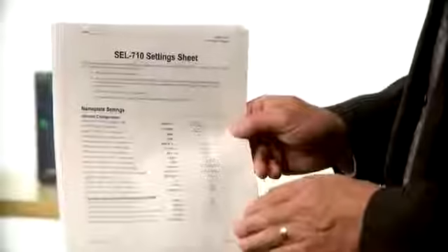So after pulling that information off of the one-line diagrams, I went through and just pulled out the motor data sheet. Basically, all the information we need to set the motor nameplate application in the relay is provided on this nameplate application data sheet right from the motor manufacturer, including the full load current and any of the other pertinent information we're going to need to set the relay. So I went ahead and pulled all this information off those sheets, and I filled out my nameplate application setting sheet with all the information I need to set the relay. So let's go ahead and do that.